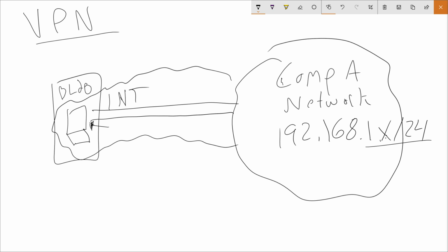So that's method one. What are the pros of a VPN? The pros are that it extends the network, so the traffic from end to end is encrypted and secure, and most importantly, the IT group can monitor what's going on because it's their network being extended. This is most common in medium to large organizations. It's as simple as installing a client, managing some login credentials, a username and password, and logging onto the VPN. Then you can use the BAS software on your laptop to connect to a BAS server. That's the most common one.